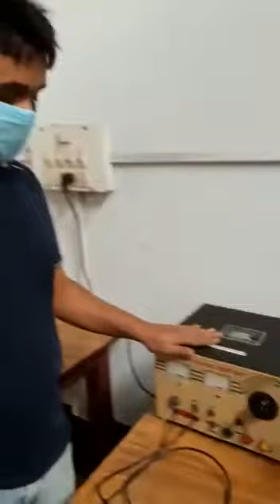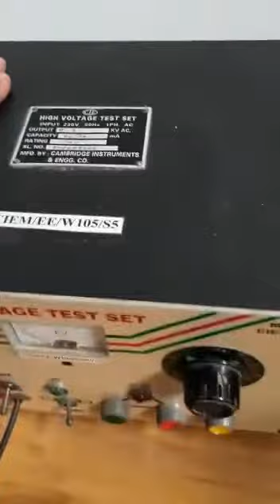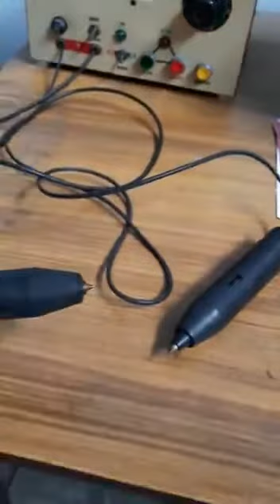Today we will see how to measure breakdown voltage of solid insulators. For this purpose, we have a high voltage test set, which gets input from the line voltage. Inside it we have a high voltage transformer, and the secondary side of that auto transformer is brought outside through two electrodes. We have to place an insulator between these two probes and apply voltage through this variac.